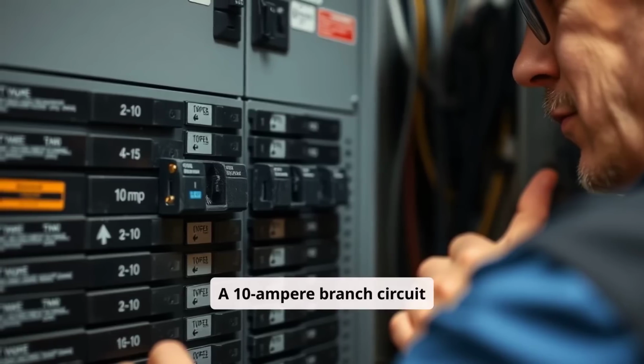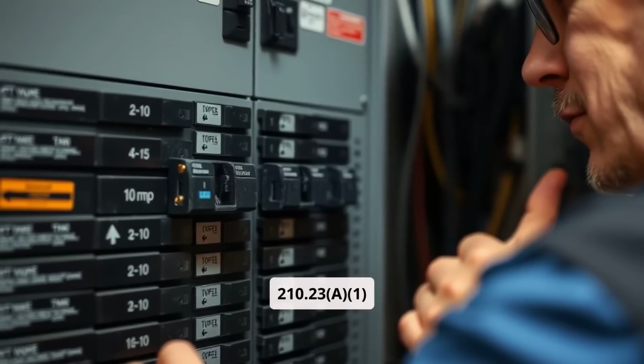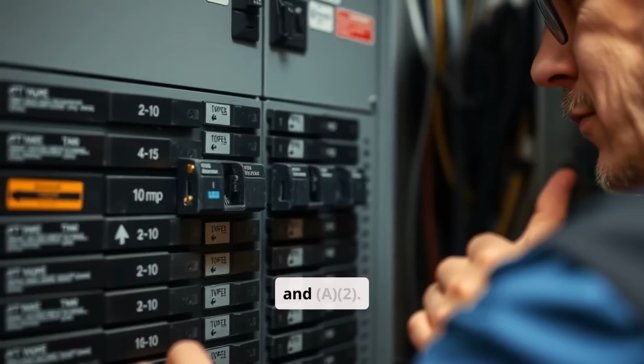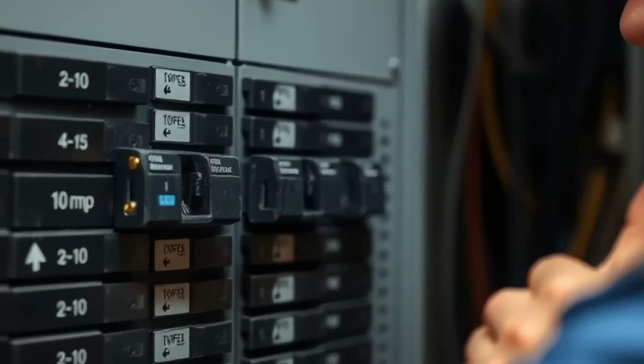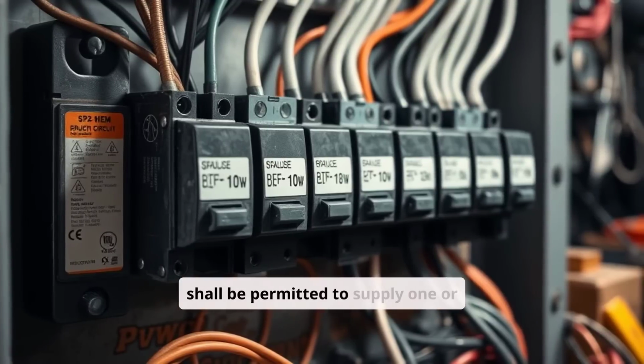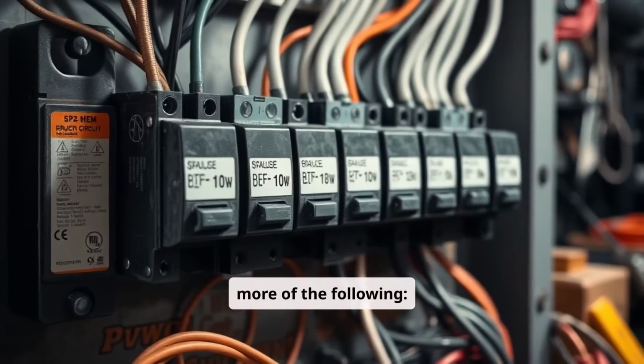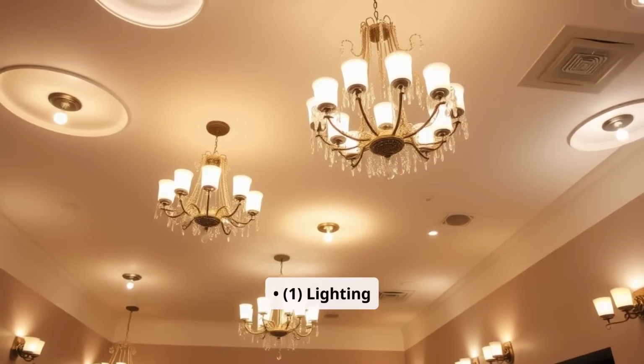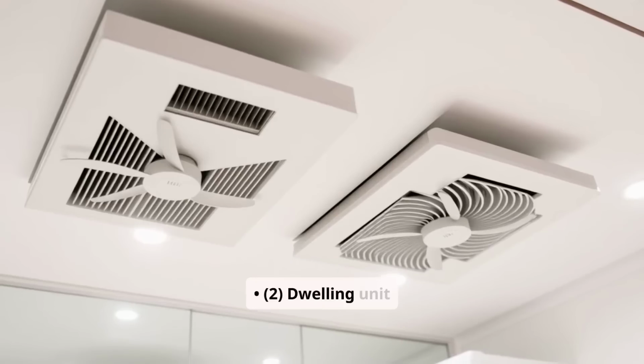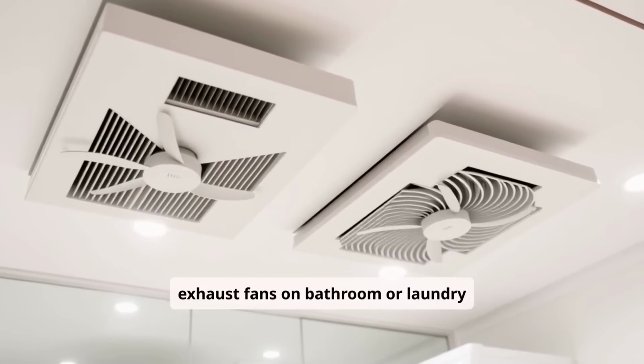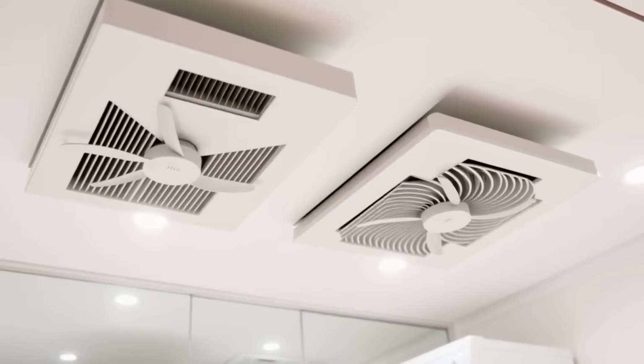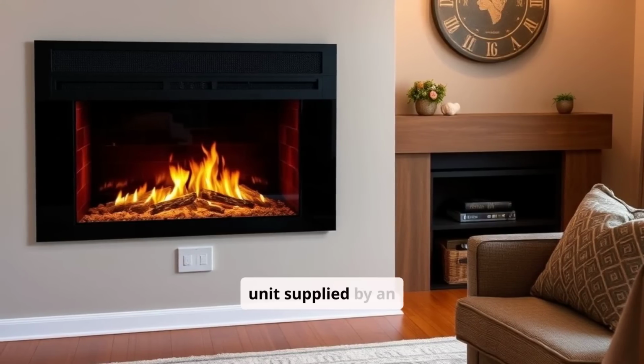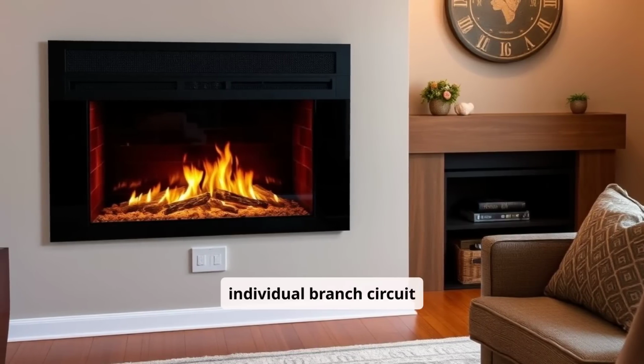A 10 ampere branch circuit shall comply with the requirements of 210.23(A)(1) and (A)(2). A 10 ampere branch circuit shall be permitted to supply one or more of the following. 1. Lighting outlets. 2. Dwelling unit exhaust fans on bathroom or laundry room lighting circuits. 3. A gas fireplace unit supplied by an individual branch circuit.